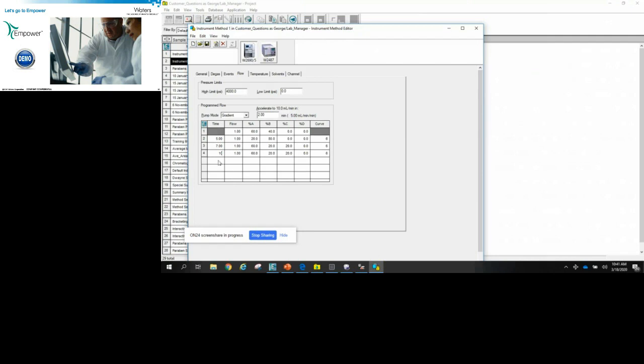So what I can do is put one additional line in my instrument method for the pump, and I can say at 30 minutes, lower the pump flow rate to 0.1 mL per minute using curve 11. What curve 11 tells Empower to do, or what Empower tells the pump to do at that point, is only make that change at the end of the time segment.